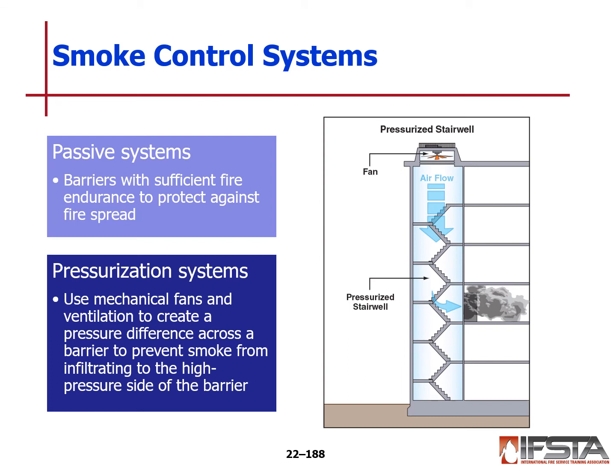So with these systems, you may have a pressurized or a passive system. With passive systems, barriers with sufficient fire endurance are there to protect against the spread of fire and will help control the smoke. In a pressurized system, we use mechanical fans and ventilation to create a pressure difference across the barrier to prevent the smoke from infiltrating to a high pressure side of the building. And so these work well, and we want to keep smoke out of the egress areas. An example in a high-rise building would be the stairwells.